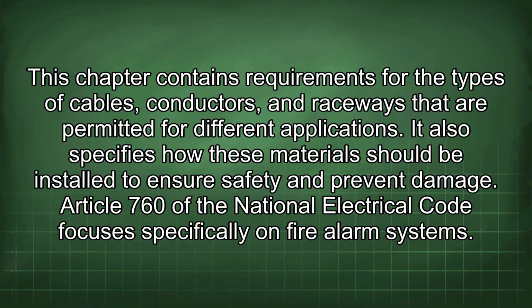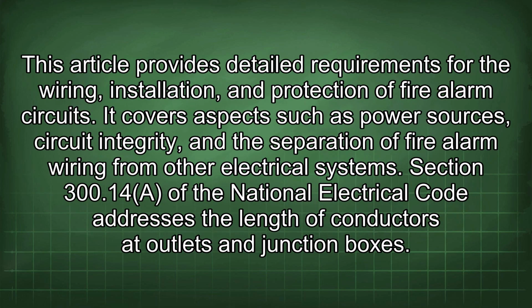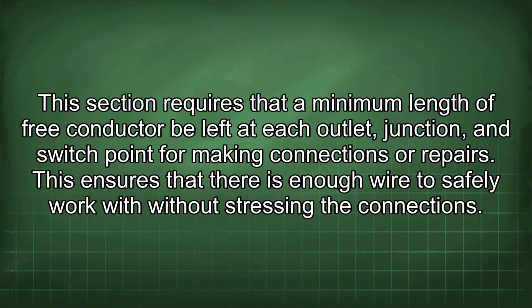Article 760 of the National Electrical Code focuses specifically on fire alarm systems. This article provides detailed requirements for the wiring, installation, and protection of fire alarm circuits. It covers aspects such as power sources, circuit integrity, and the separation of fire alarm wiring from other electrical systems. Section 300.14 of the National Electrical Code addresses the length of conductors at outlets and junction boxes. This section requires that a minimum length of free conductor be left at each outlet, junction, and switch point for making connections or repairs. This ensures that there is enough wire to safely work with without stressing the connections.